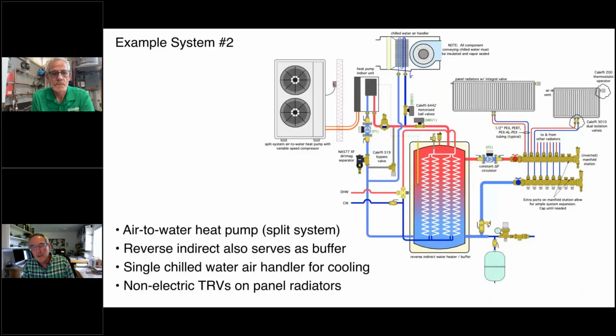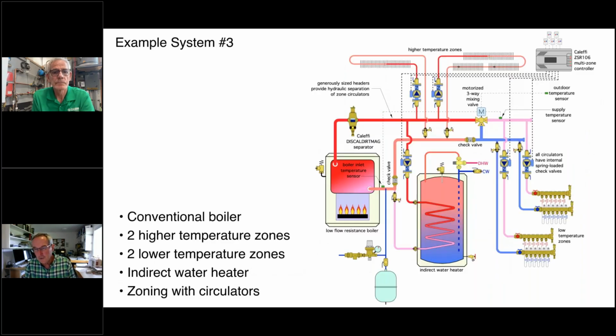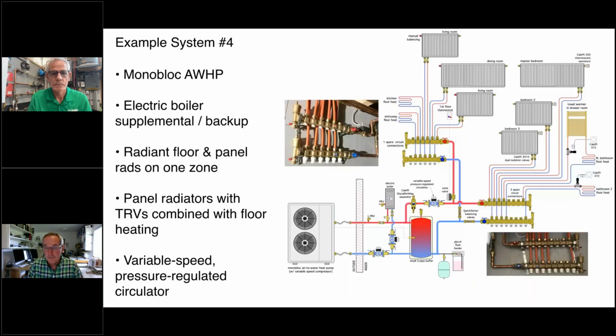Another system, 2 zones, a high temperature fin tube, 2 zones of low temperature radiant panel heating, an indirect water heater. We've got a Discal dirt mag. This is a combination of air separation and dirt and magnetic particle separation. We've also got, let's see, a motorized mixing valve that is controlling the water temperature to these lower temperature zones. So again, we're zoning with circulators in that case. This is actually a system from a house I helped build for my daughter. It's using a lot of different zoning techniques in here.